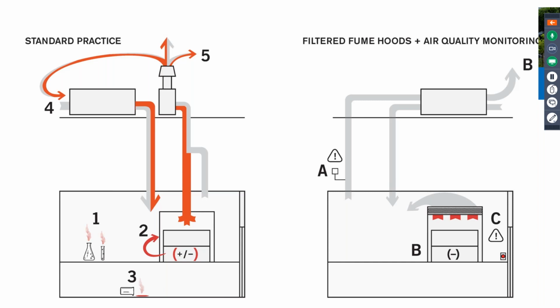So instead of that, we were able to install an air acuity system that monitors the air quality in the space. And therefore, when it's clean and safe, we're running at 4 air changes per hour instead of the typical 6. And at night, we're running at 2 air changes per hour. And we're monitoring the air quality in the space and providing feedback to the users. So if they are accidentally exposing themselves and releasing chemicals into the air, there's actually a feedback system to tell them that, rather than just flying blind and not having any information.